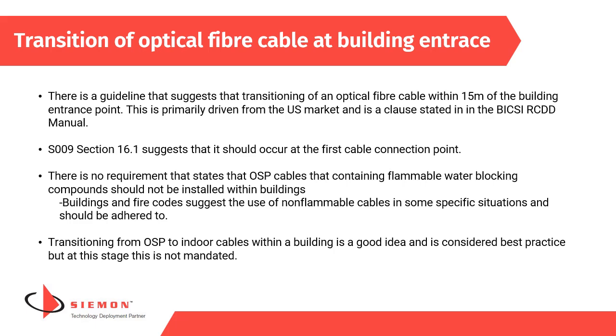Note 1 states, and I quote, "There is no requirement in this standard to change the cable type where an underground or aerial cable enters a building. However, any cable used within the building past the first cable connection point should meet Clause 5.6.4 of S008." My suggestion is that if that first connection is not really close to where you enter the building, you should be checking with a building inspector or a fire inspector before running a cable any distance which puts people and/or the building at risk.